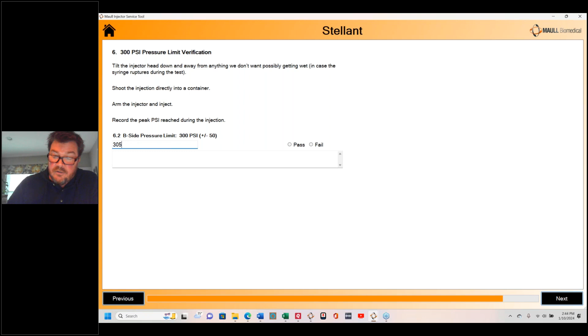And then when we're finished, it's just something due to the nature of how MedRad does some of their contrast injectors. They'll have a little message pop up if it's near its PM procedure. So what we'll do is, first we hit the reset button to blank it. Any protocol we had on here during our testing, we didn't want to leave it for the operator. So we hit the reset button, and that brings it back to this default flow rate of 1, volume of 1 on the contrast side. And then we're going to go into the service menu, and we're going to change the calibration date on it. We're just basically going to set the calibration date 2 years out.